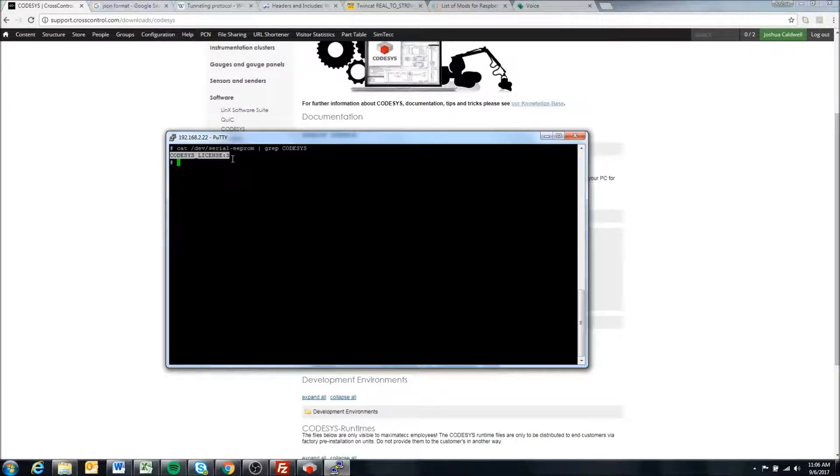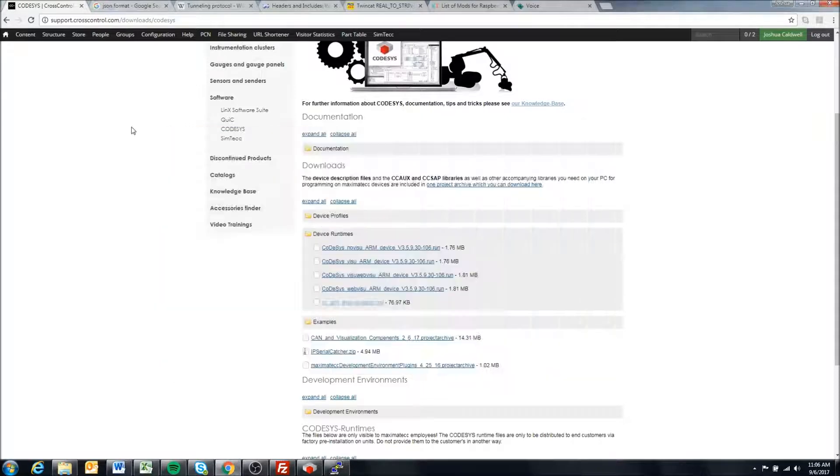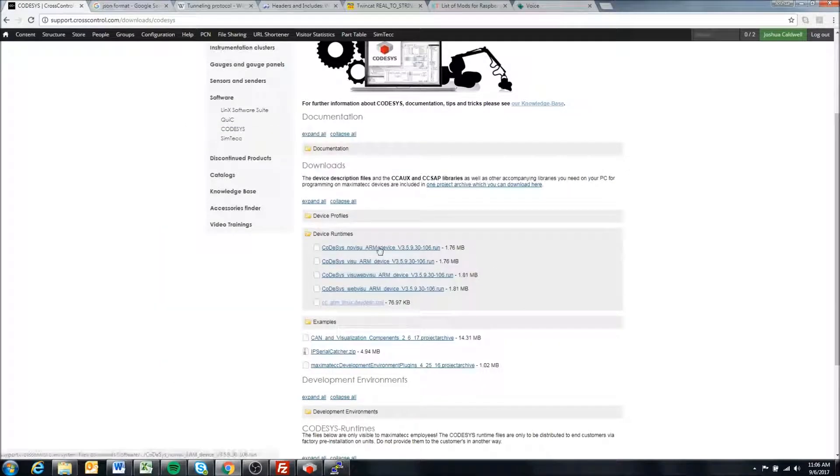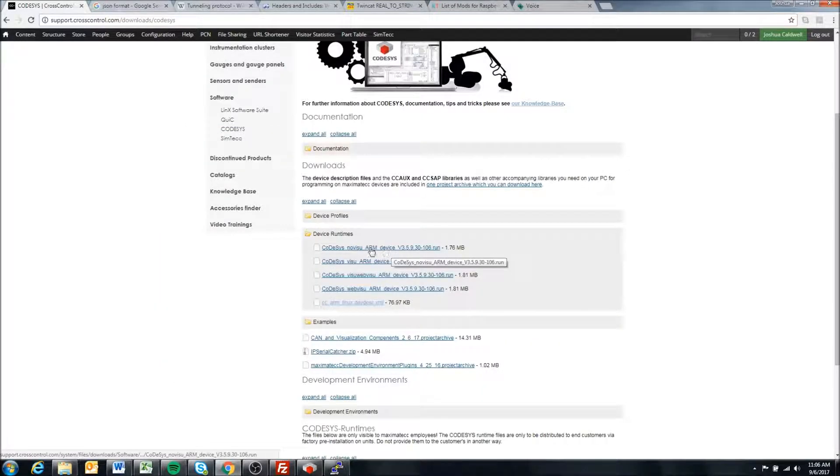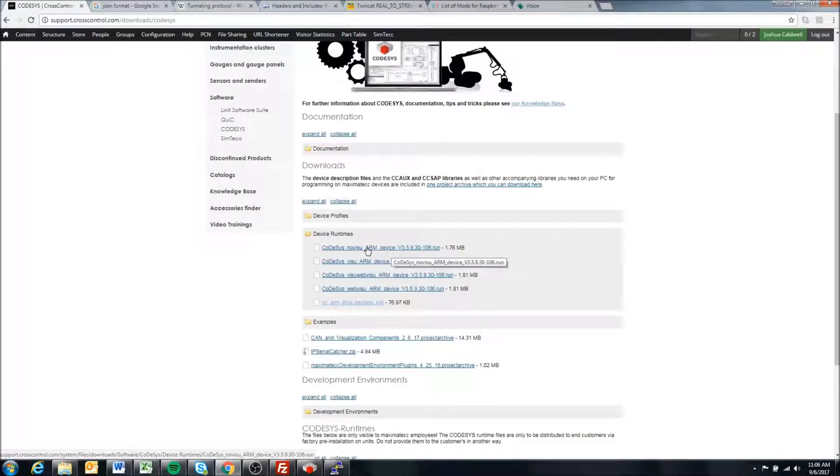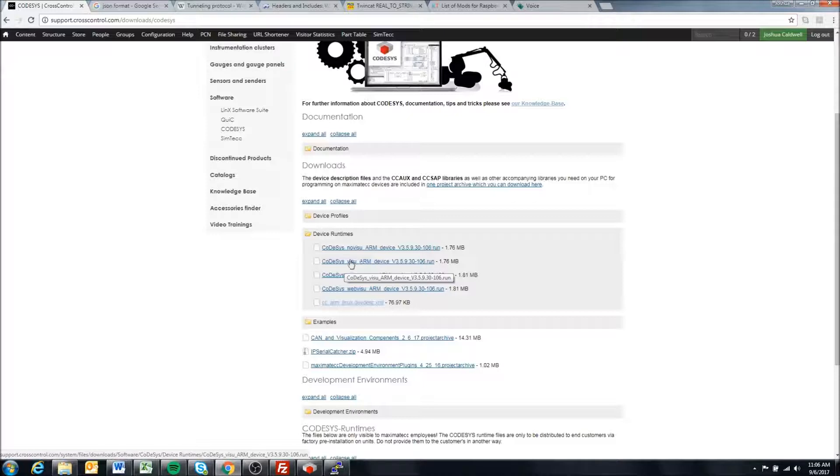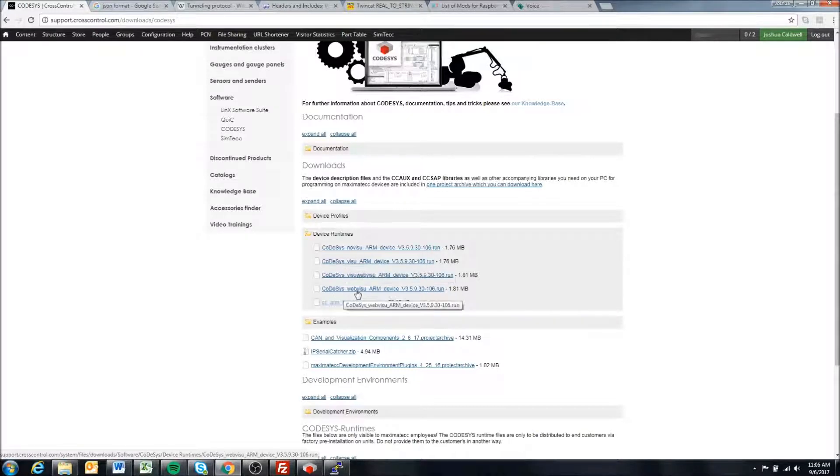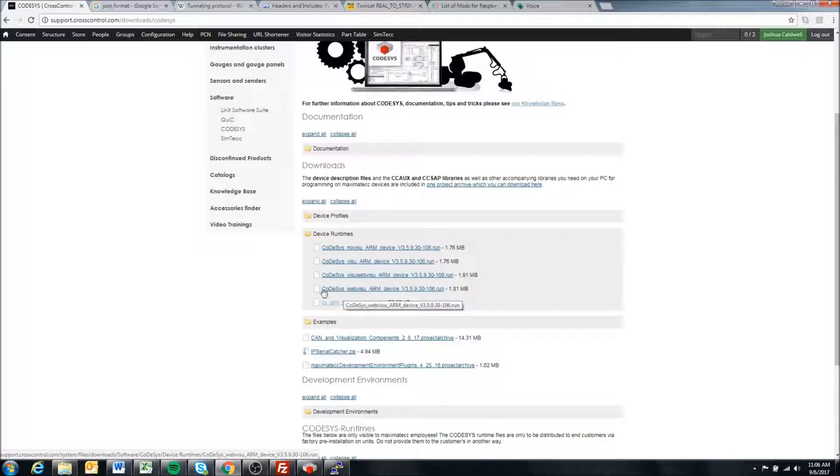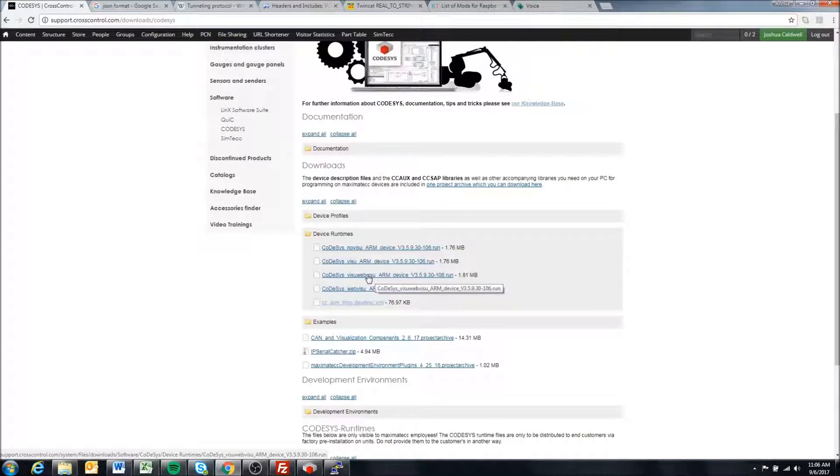Right now we're on codesys_license 3. The numbers represent what we see here. A codesys_license 0 is a non-visu license, so no visualization. A codesys_license 1 is visualization. A codesys_license 2 is only web visualization, and codesys_license 3 is visualization and web visualization.